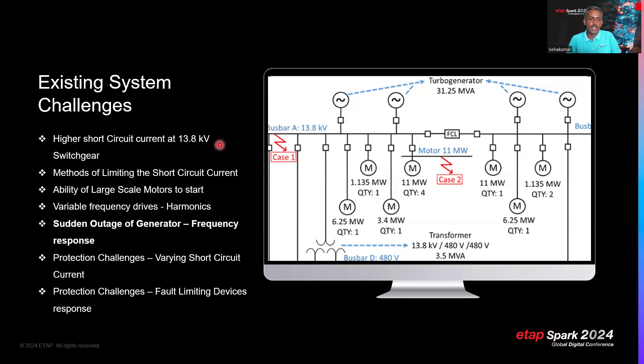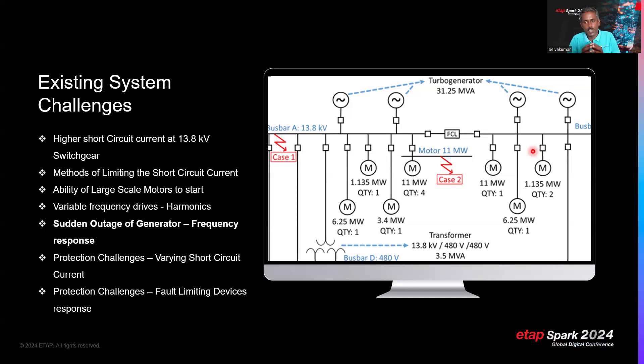Critical clearing time must be determined from transient stability studies, and faults must be isolated well within that critical clearing time. These are all challenges in the conventional FPSO itself. ETAP is used worldwide for such FPSO system design and delivers excellent results. Now, what is new?